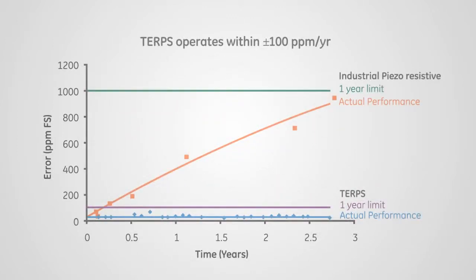All of these innovations come together to deliver exceptional performance. Test results show that the error over a wide temperature and pressure range never exceeds 0.01% FS. Stability data over two years show that TERPS operates within a plus-minus 100 ppm per year.